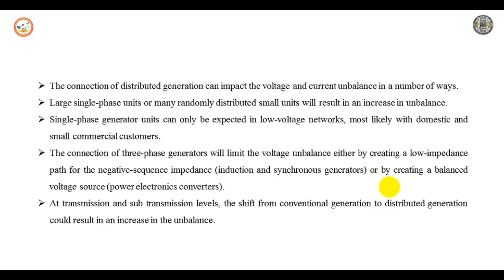When more distributed generation is producing power, fewer large conventional generator units will be in operation. The result is a reduction in short circuit capacity at transmission and sub-transmission level. The same unbalanced current will give more unbalanced voltage. The two main sources of unbalanced voltage at transmission level are as follows.